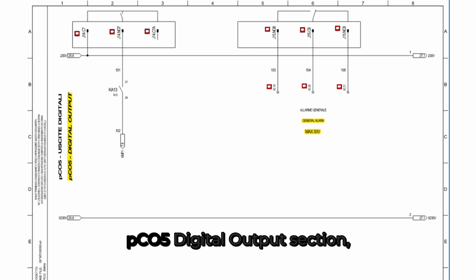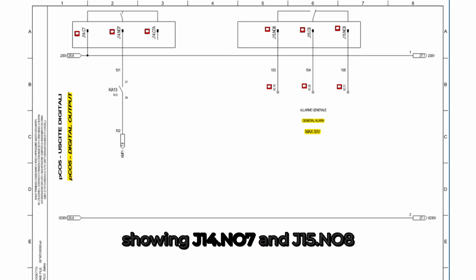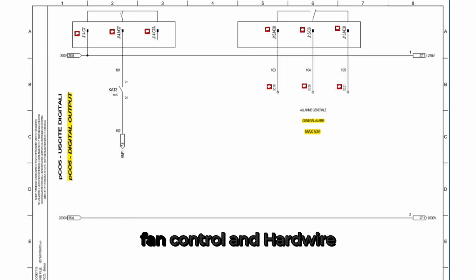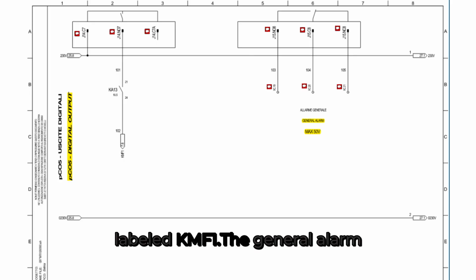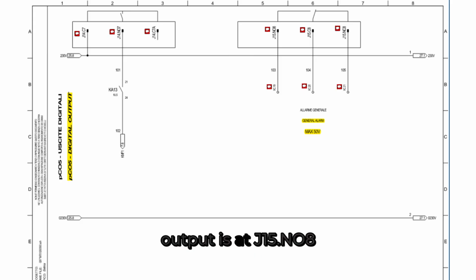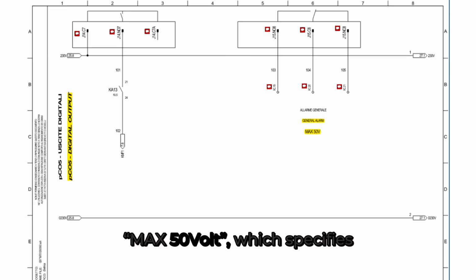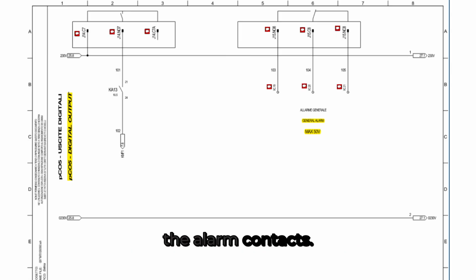This page continues under the pCO5 digital output section, showing J14.NO7 and J15.NO8, which manage two key functions: fan control and a hardwire connection for the alarm signal of the heat pump. The relay output J14.NO7 energizes KA13, a relay, which in turn drives the condenser fan contactor, labeled KMF1. The general alarm output is at J15.NO8, and the field wiring terminal for that is XC19, XC20 for a normally open contact. There's also an important note on this page, max 50 volt, which specifies the electrical limitation of the alarm contacts.